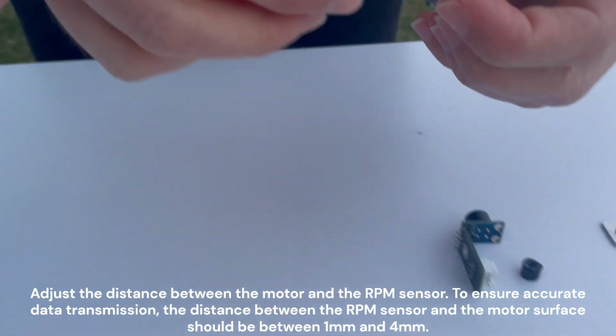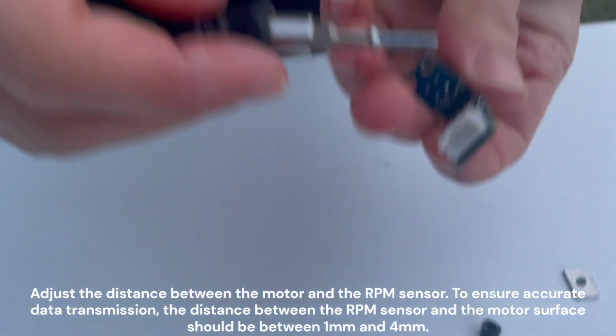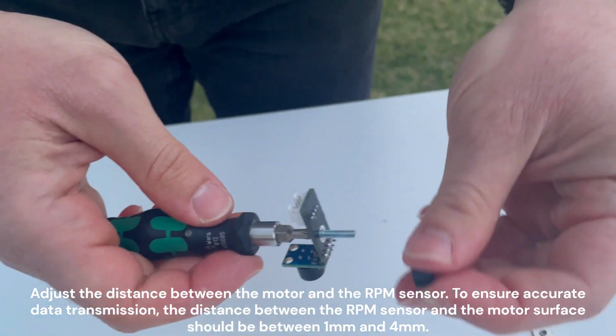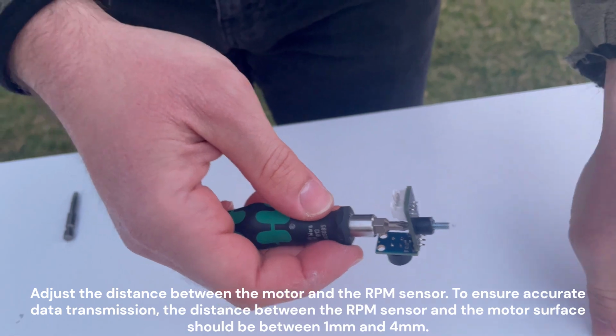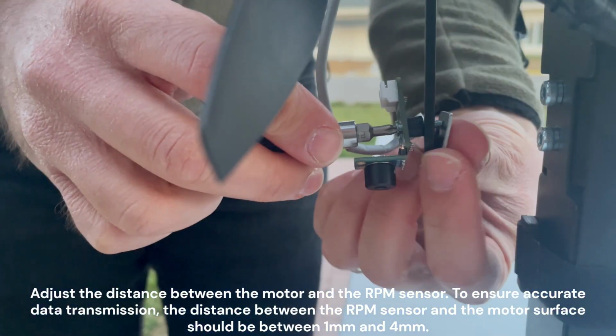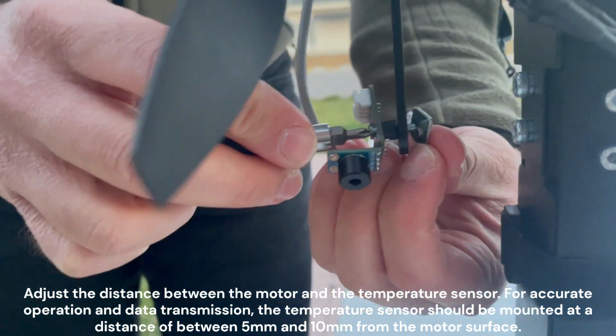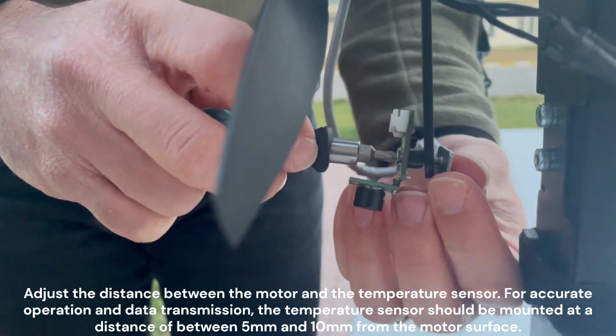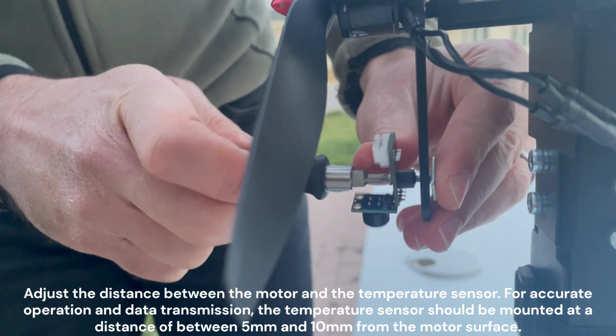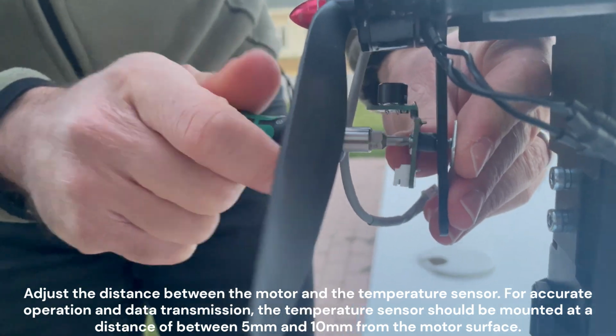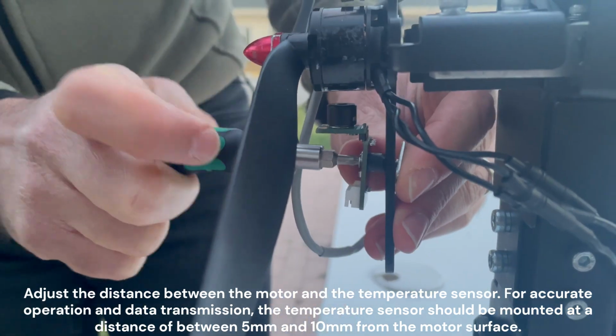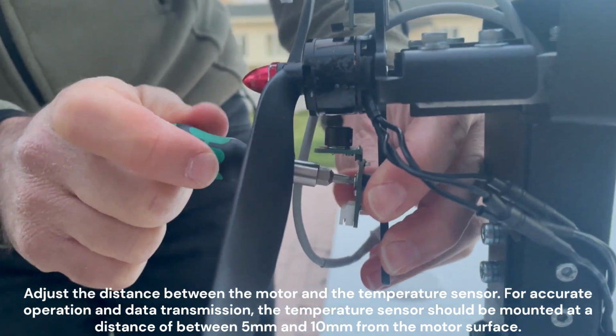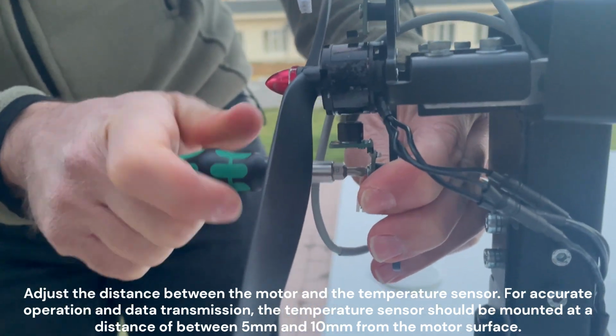Adjust the distance between the motor and the RPM sensor. To ensure accurate data transmission, the distance between the RPM sensor and the motor surface should be between 1 mm and 4 mm. Adjust the distance between the motor and the temperature sensor. For accurate operation and data transmission, the temperature sensor should be mounted at a distance of between 5 mm and 10 mm from the motor surface.